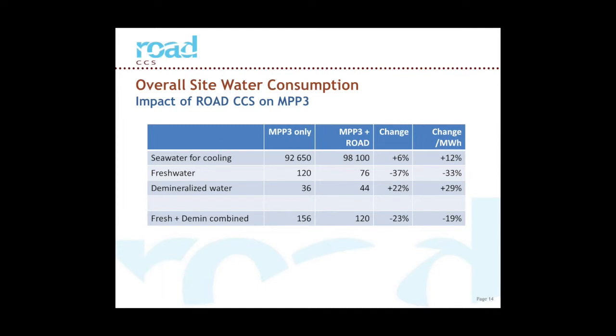You can see that the freshwater consumption has fallen because we've recycled the condensate collected from the direct contact cooler, which is the condensate extracted from the flue gas. The demin water consumption has gone up. It's unusual for a power plant to have separate freshwater and demin water supplies. It's more usual for them to do their own water treatment and have a single water supply. So I've put a line here which is simply a combination of those two to show what's more typical of a power plant, and what you see is a 23% reduction in the freshwater supply, which is very close to the percentage of carbon capture we have on the power plant.